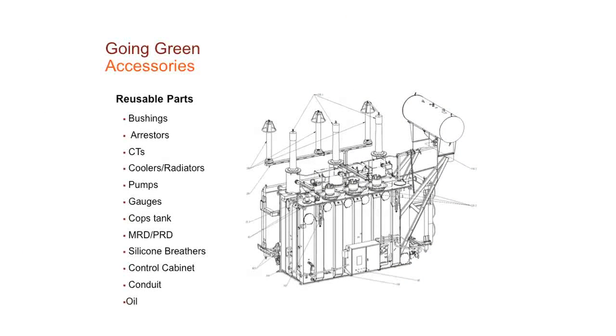Other items that are typically reused for transformers. You can usually reuse the bushings. If not, you can purchase new ones, and we'll recycle the bushings themselves. Arresters, CTs, coolers and radiators, the pumps, gauges, the COPS tanks.